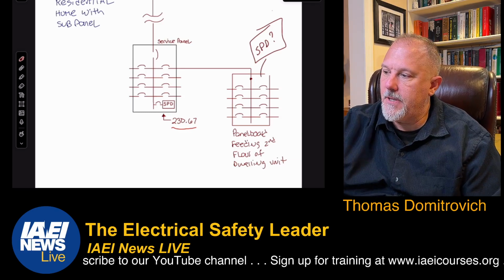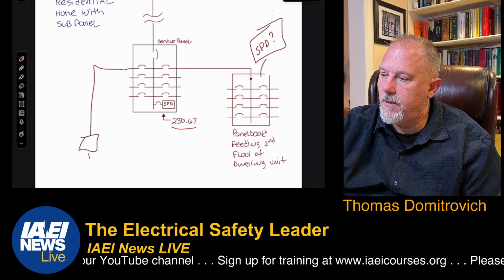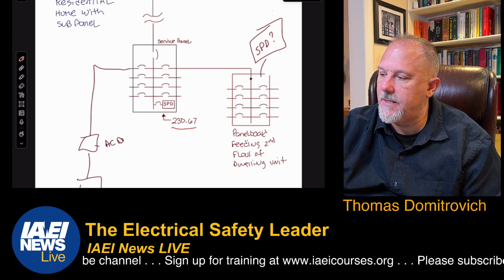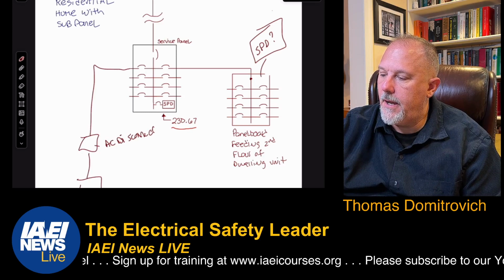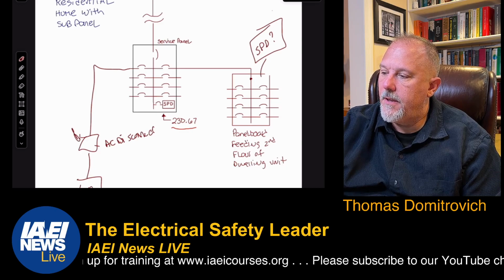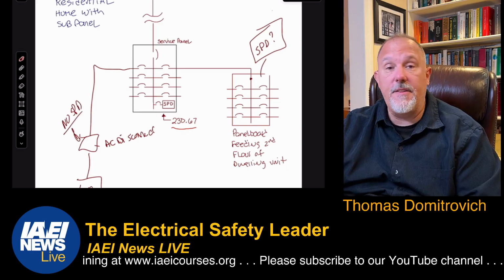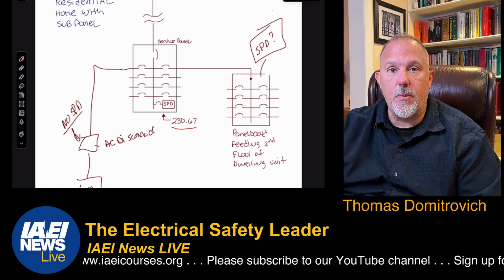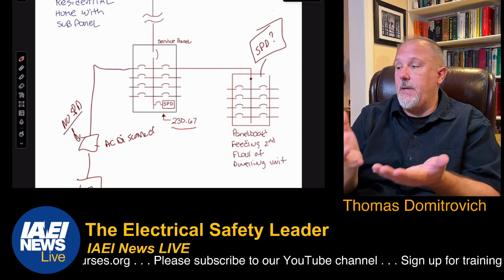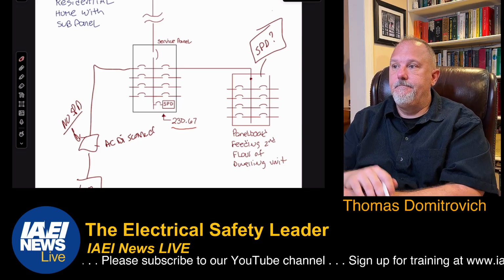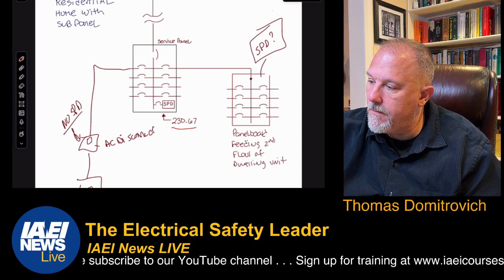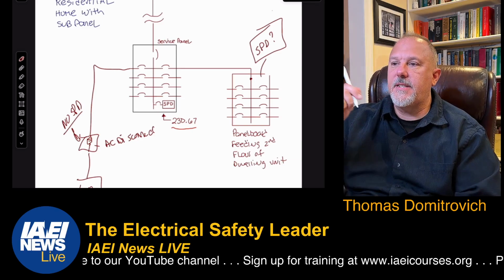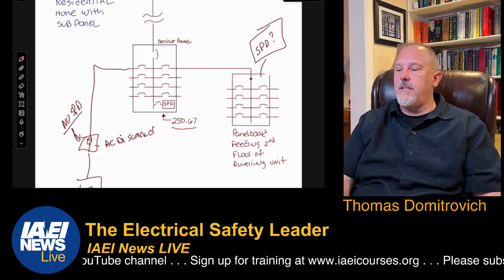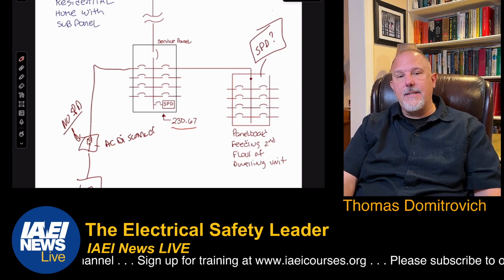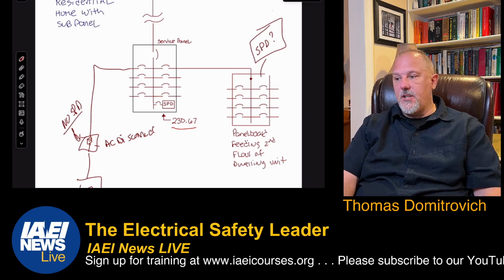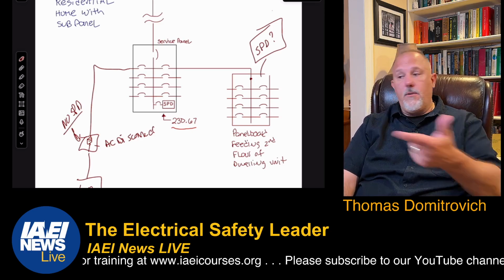And oh, by the way, somebody else pointed out, I could come down to an AC disconnect and then go to HVAC. No SPD would be required there. Although it's a feeder going to a disconnect. And what's the difference between a disconnect and a panel board? If there's a fuse in here, right? So if there's a fuse in there, because it says that contains branch circuit overcurrent protective devices. So if I have an AC disconnect with a fusible AC disconnect going to HVAC equipment, then I would say, oh, you need to put a surge device there.